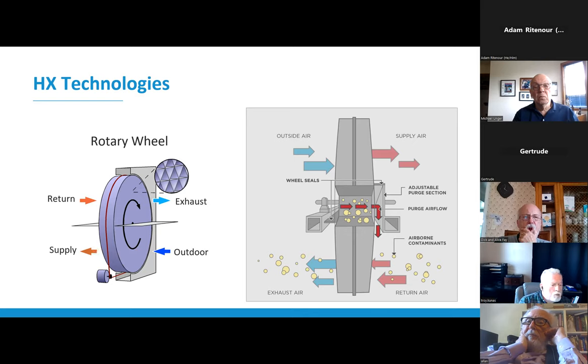One thing that's important to note here is that these rotary wheel technology units must have a purge section, and that's basically to get the return air completely out of the wheel before the outside air starts coming in and supplying pre-warmed fresh air from outside. And that's just to keep that EATR or leakage rate low.